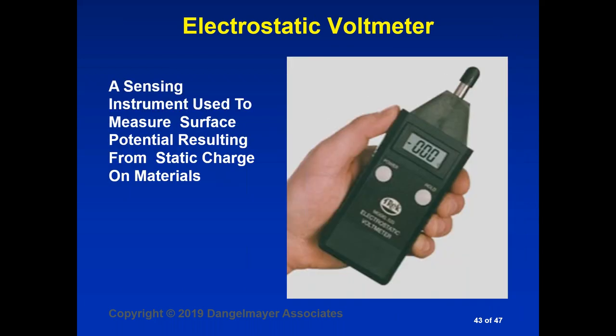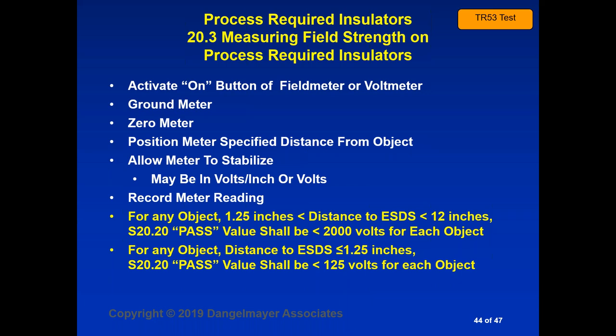The electrostatic voltmeter, on the other hand, is usually able to measure at much smaller distances. It may have the same ratio between distance and measurement view, but an instrument like this can measure down at 1/10 of an inch, so that you're actually looking at an area less than half an inch in diameter. So you'd use an electrostatic voltmeter. You could use it to measure large surfaces, but it's particularly helpful when you're measuring very small surfaces. So you're going to be looking for the charge on your isolated conductors with either of these two instruments.